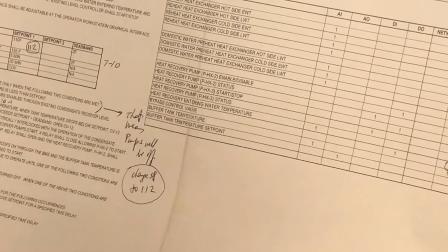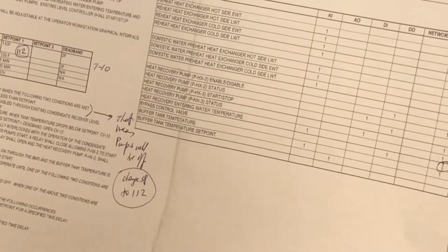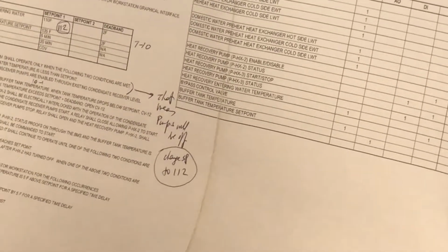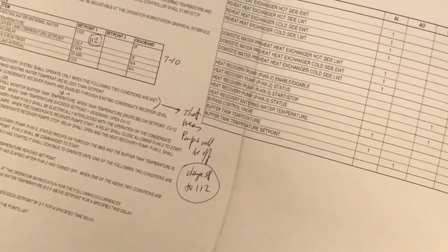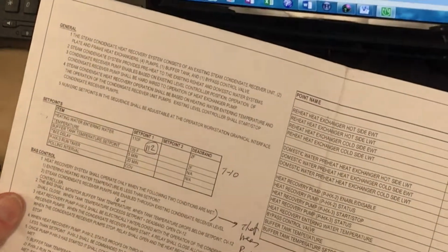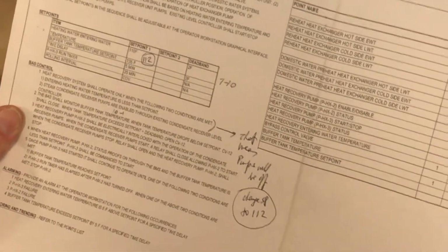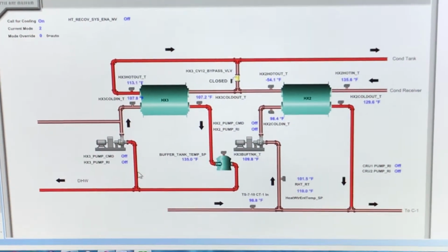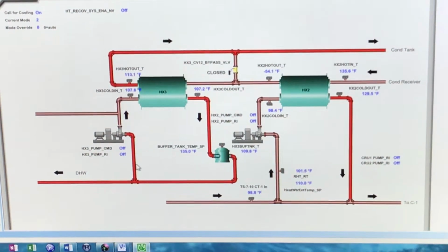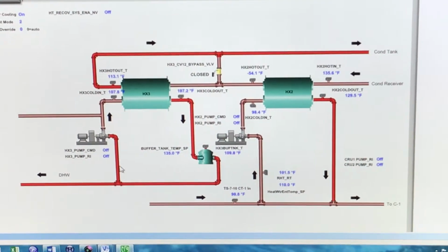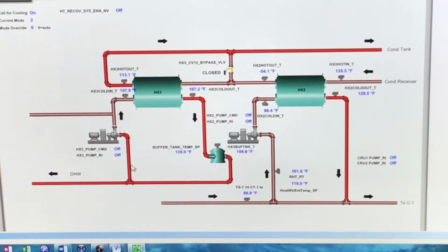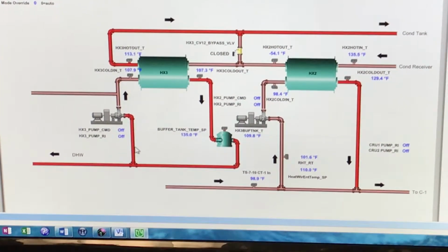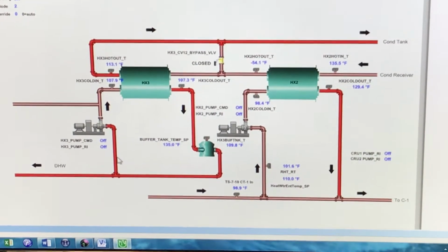Before you try to cool it down, why not take some heat out? That is exactly what the two-way heat exchanger is trying to do. It actually serves the domestic hot water loop on the left-hand side, and it also tries to boost the heat recovery, or the heating loop, a little bit. So the right side is the heating loop, and the left side is the domestic hot water. And the tank temperature is for the domestic hot water too, correct? Yes. We don't want that temperature too high, so there is some sort of alarm or limit, and when it gets too high, I think you bypass the valve and disable that, or reduce the flow of steam through that heat exchanger.